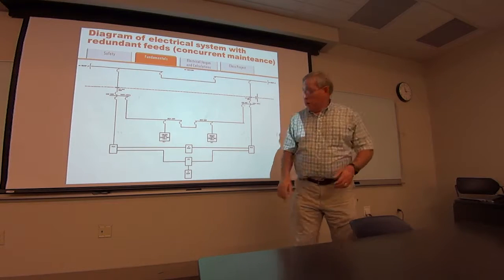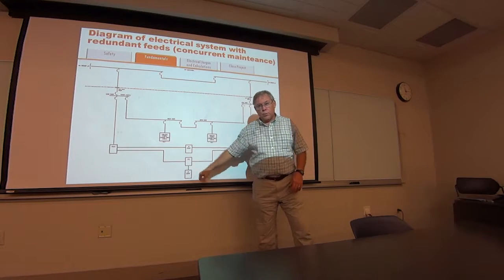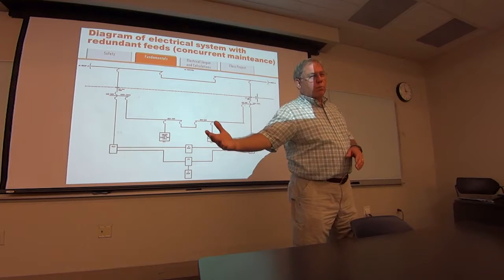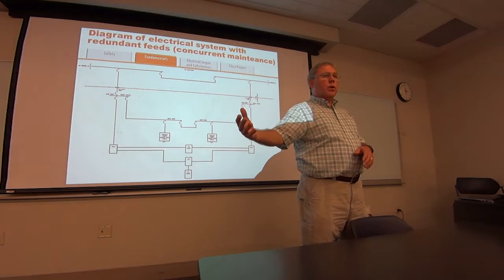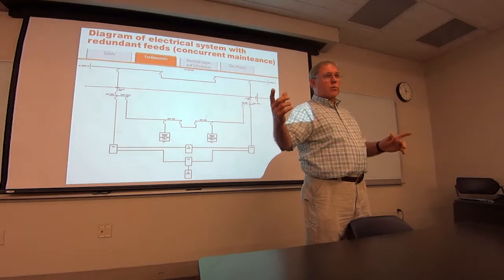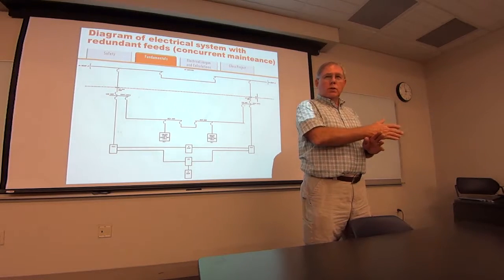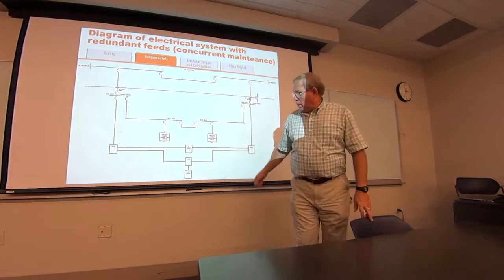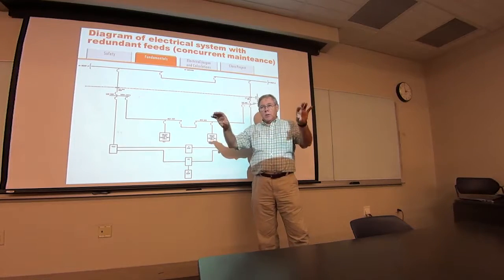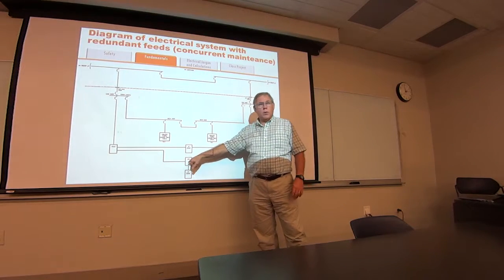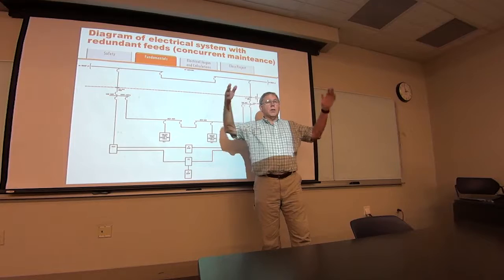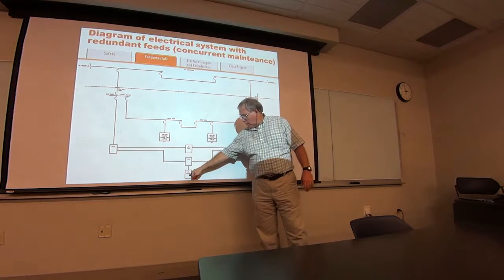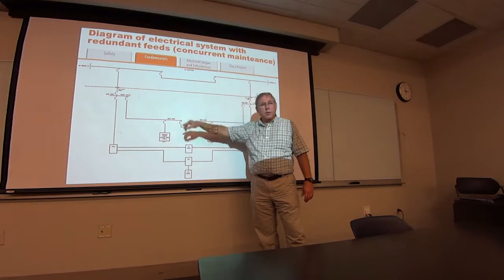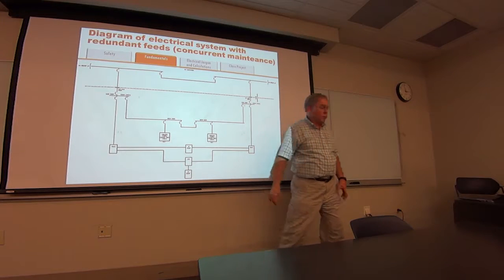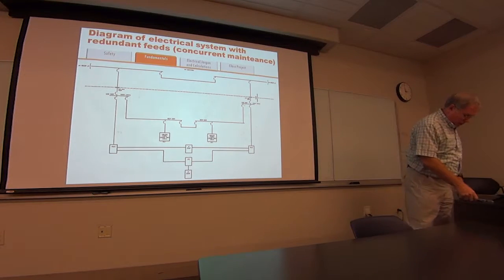You can also buy something called a static transfer switch that will draw the load off one side, and if it goes away within a quarter of a cycle, 4 milliseconds, switches over to the other side for you. And you can buy these in little rack mounted jobs. You can buy big 600 amp 480 volt jobs that are just full of electronics. And if you got a single corded load and you want all this reliability, you have to do something like that. And I know places where they've done that a lot.